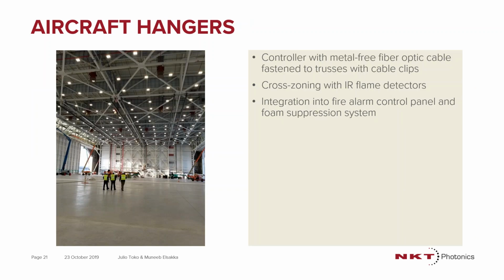For airport hangars, really the asset is very, very expensive. It's very important to go with the code, but most importantly, we also know we're dealing with other forms of detection systems. So IR flame detectors, for instance, are used as well. So the ability to pair, as a complementary solution, the fiber optic linear detection with these other systems to be able to, let's say, activate the foam dump or the water mist after or before a catastrophic event is very, very important. An example is the cross zoning can be done very, very easily and virtually.